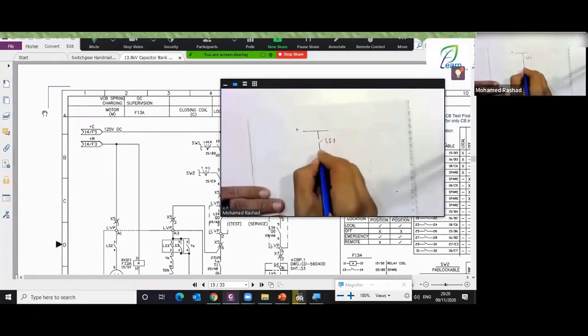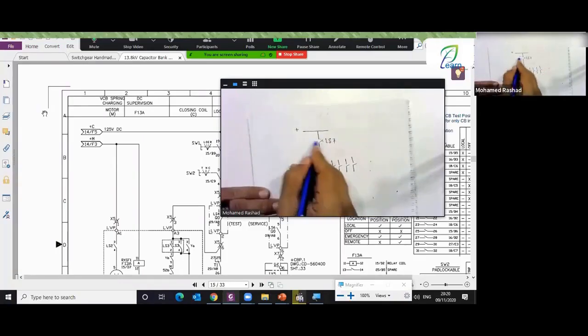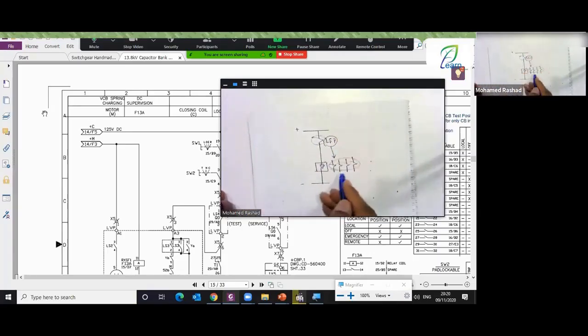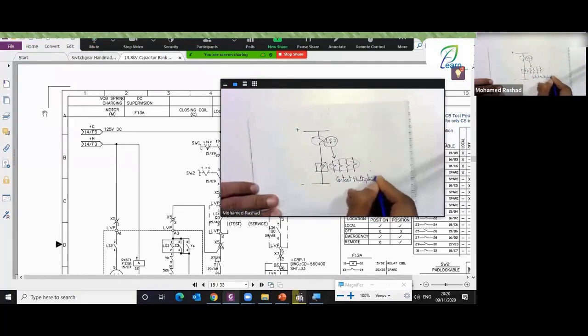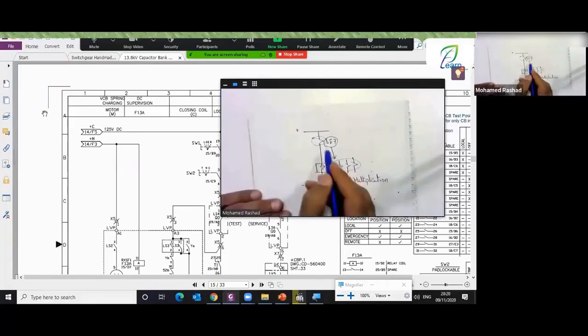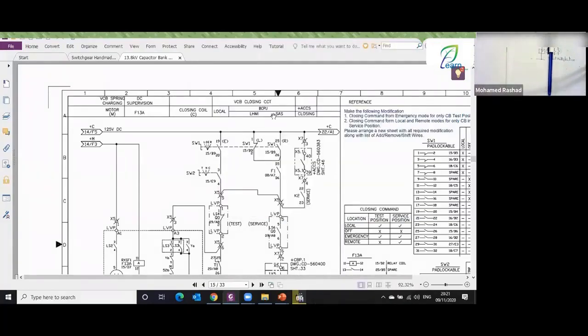It operates the relay XOR. This is, of course, a coil, and this coil has contacts, normally 2, 3, 4. So when this closes, this one operates, and then all of these close. So all of these have closed when this one closes, right? It's as if I have turned this into 4 copies, each one used in a different circuit. We call this contact multiplication. Contact multiplication means creating copies of the same operation method of this limit switch. All right, engineers, very good. So this is our story with contact multiplication.